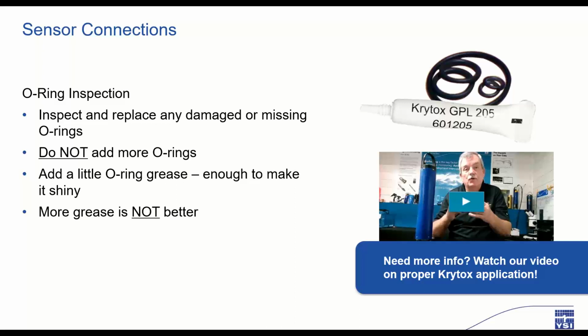Start with a visual inspection of the O-rings, looking for wear, nicks, or cuts, as well as dirt or debris under or around the O-ring. It's just as important that we inspect and clean the mating surface where that O-ring is going to seat. Something as simple as a hair across this area will compromise an otherwise perfectly good O-ring. If the area around the O-ring is dirty with debris, you can use a toothbrush to gently whisk that dirt away from this area. Then apply a dab of Krytox grease to your fingertip, and using your finger, apply the grease to the O-ring so that as you apply the new grease, you can feel for nicks, cuts, and malformations in the rubber. If you find any defect, replace the O-ring at once.